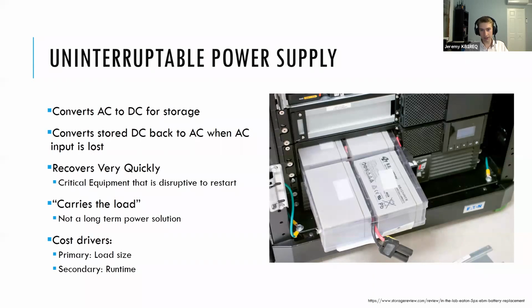Our radios boot pretty quickly. Generally speaking, there's no detriment to them. You know, if they were to lose power for 30 seconds or something like that, we can get those back up and running fairly quickly. But if we think of something like a repeater, especially one that may have a microcontroller or something that could take several minutes to boot and is primarily an AC device, that is definitely more of a candidate for a UPS, because you're preventing that reboot from happening. And that's what a UPS can do, is it prevents that device from ever seeing any power loss.